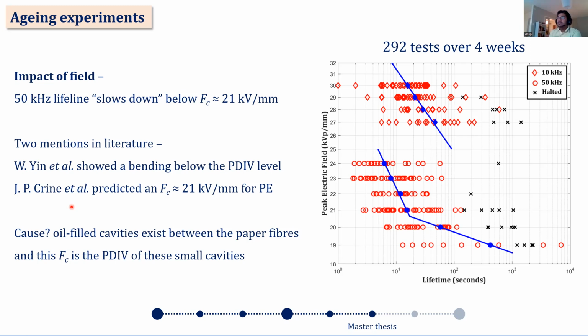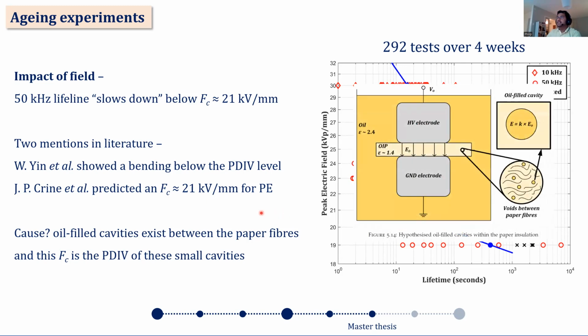What we came up with as the cause for this line was that if you look at the paper fibers of the OIP itself, there could be oil-filled cavities within the paper fibers. And this critical field, Fc, is essentially the inception level of these small cavities, because they would have field enhancement. If you go above it, it would cause faster failure, and if you go below it, it would be slower failure.